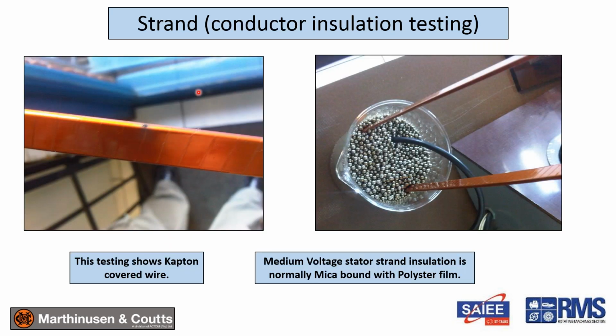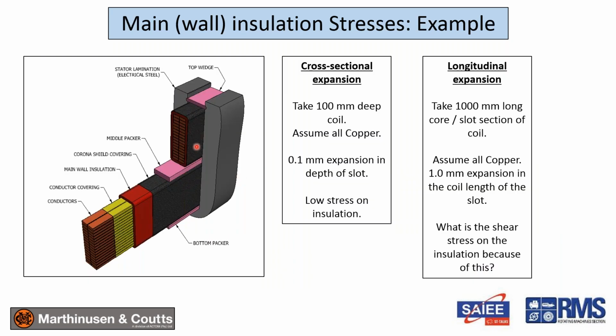So this is your strand insulation. It normally takes very low voltages except under transient conditions, but it's still important to test it. The average repairer, even OEM, doesn't do testing of their conductor. They rely on the suppliers, but this was some testing that was done a couple of years ago where you dip the conductor in and you can see where it fails. You have different types of taping, butt lap, half lap, etc., and this shows Kapton covered wire. So strand insulation is very important, but as I mentioned, the presentation is concentrating on a specific aspect of insulation, and that's the main insulation, and that's this insulation over here.